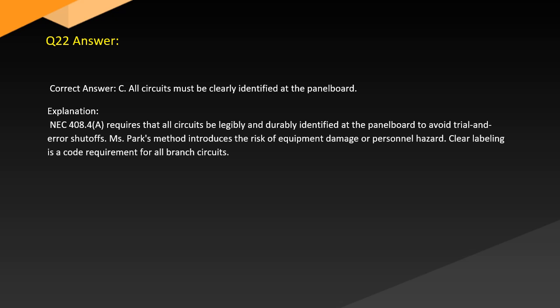Answer. Correct answer: C. All circuits must be clearly identified at the panelboard. Explanation. NEC 408.4(A) requires that all circuits be legibly and durably identified at the panelboard to avoid trial-and-error shutoffs. Park's method introduces the risk of equipment damage or personnel hazard. Clear labeling is a code requirement for all branch circuits.